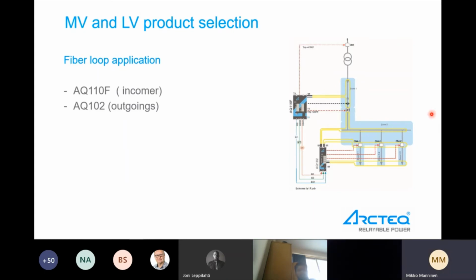There is also here one example of the fiber loop application, where one of the sensor loops is within the busbar, one of the sensor loops is with the breakers, and one of the sensor loops is with the cable ends. But if it's a low voltage board, quite often it is enough to have only one fiber. And this unit is 110F here. It's measuring the overcurrent, and it is sending the overcurrent information to the 102 unit here. And when the 102 unit is sensing the light, it will then do the trips to all these feeders.